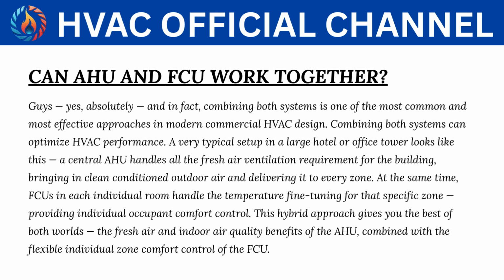Can AHU and FCU work together? Guys, yes, absolutely. And in fact, combining both systems is one of the most common and most effective approaches in modern commercial HVAC design. Combining both systems can optimize HVAC performance. A very typical setup in a large hotel or office tower looks like this. A central AHU handles all the fresh air ventilation requirement for the building, bringing in clean conditioned outdoor air and delivering it to every zone.